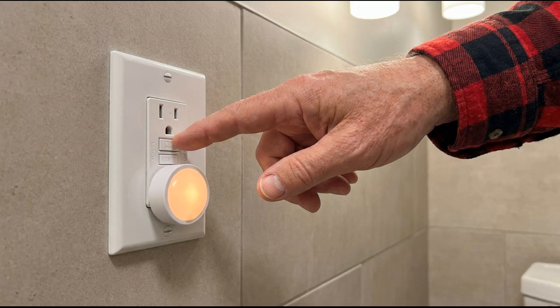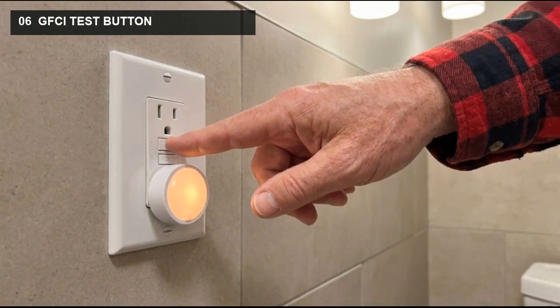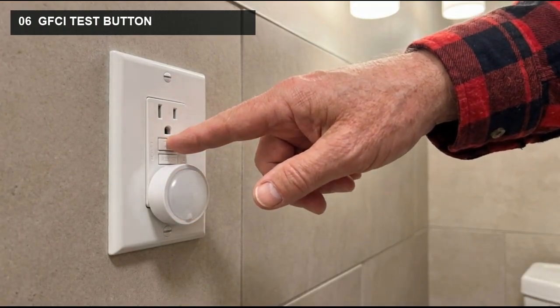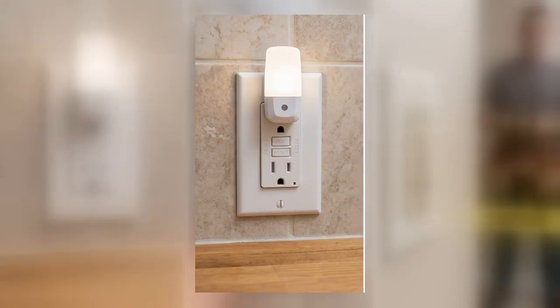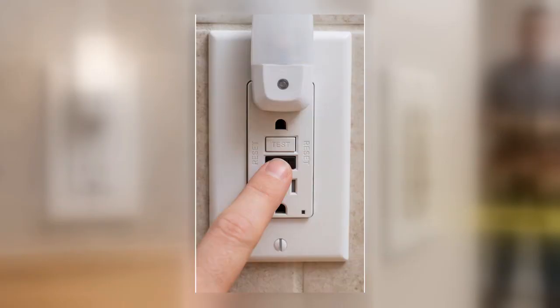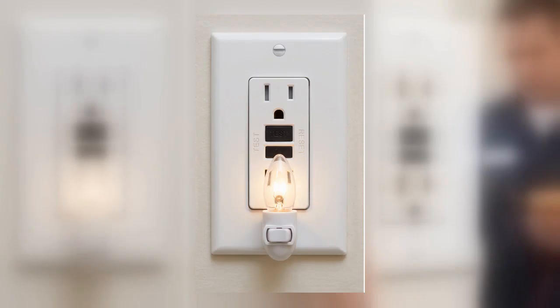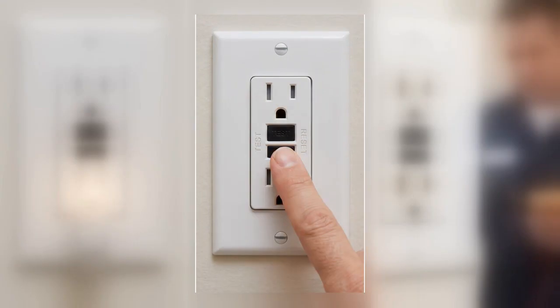If test does not cut power, reset does not restore it, either button fails, or you see heat, discoloration, moisture, hear buzzing, or smell burning, stop. Do not remove the faceplate. Replacement, repeated trips, and wiring diagnosis belong with a qualified electrician. A passing button test proves that built-in test sequence worked. It does not certify all the wiring in the house.